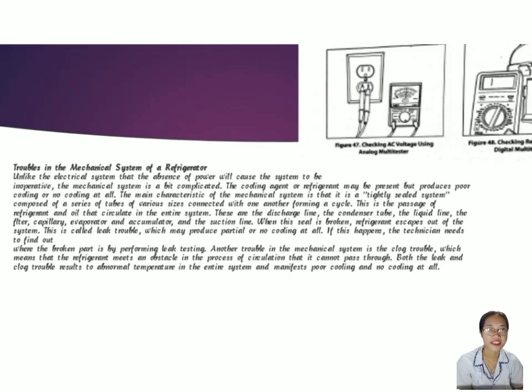Troubles in the mechanical system of a refrigerator. Unlike the electrical system, where the absence of power will cause the system to be inoperative, the mechanical system is a bit complicated. The cooling agent or refrigerant may be present but produce poor cooling or no cooling at all. The main characteristic of the mechanical system is that it is a tightly sealed system composed of a series of tubes of various sizes connected with one another, forming a cycle. This is the passage of refrigerant and oil that circulates in the entire system.